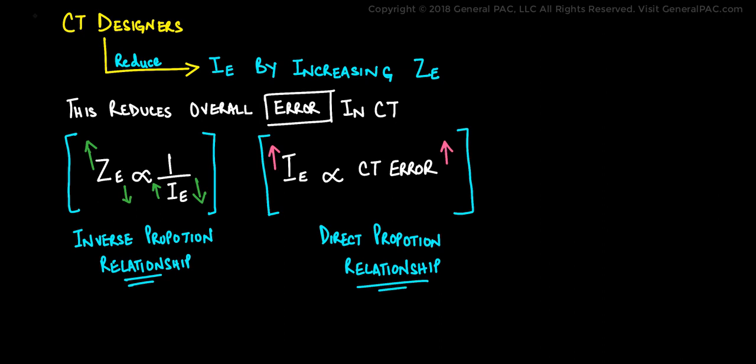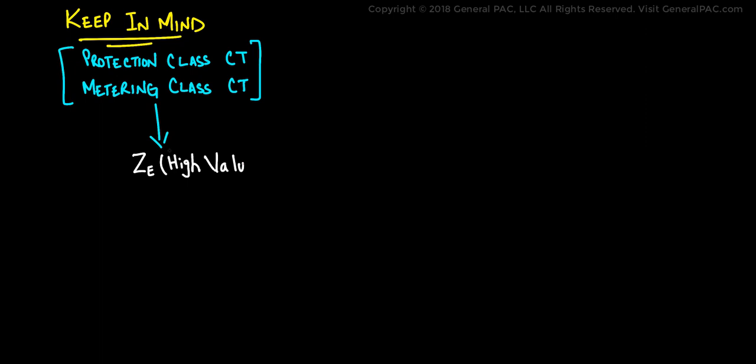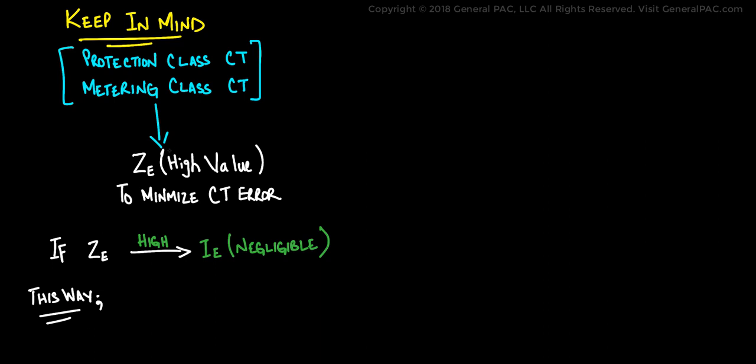So keep in mind that the protection class and metering class current transformer should be designed so that ZE is a high value. That is required to minimize the total amount of CT error. And if the value of ZE is high, the excitation current flowing through the magnetization branch will be negligible. It will be very small and we won't really see that much error or that much saturation in a CT. This way the excitation current will be low and so will the CT error produced by the current transformer.